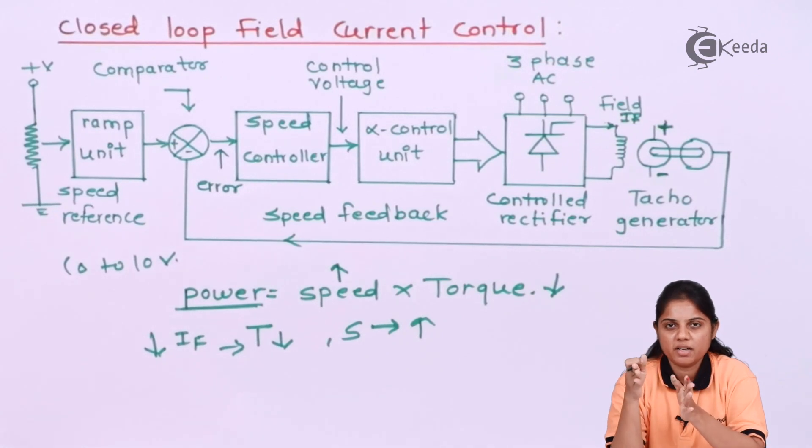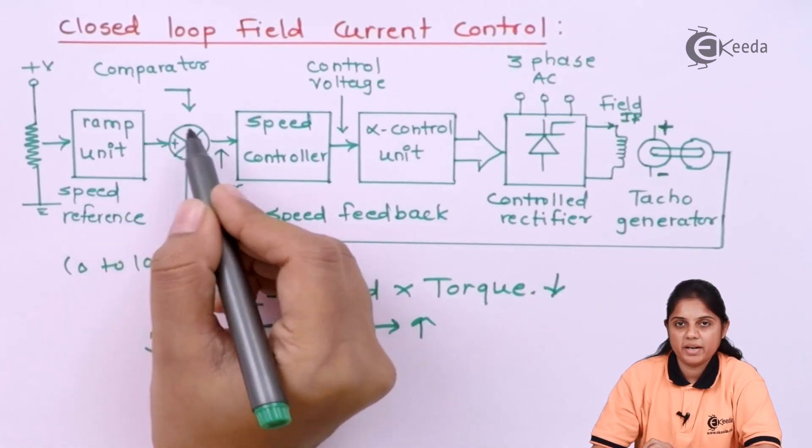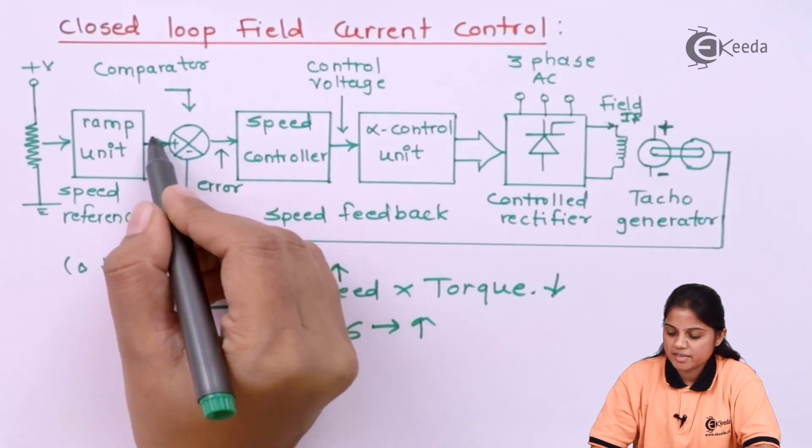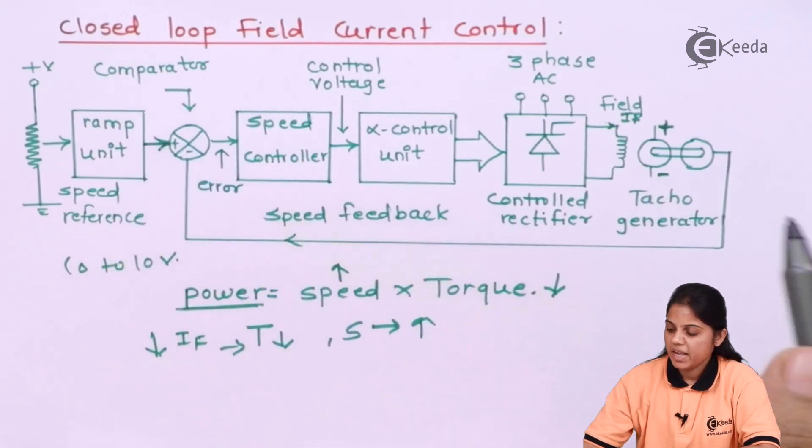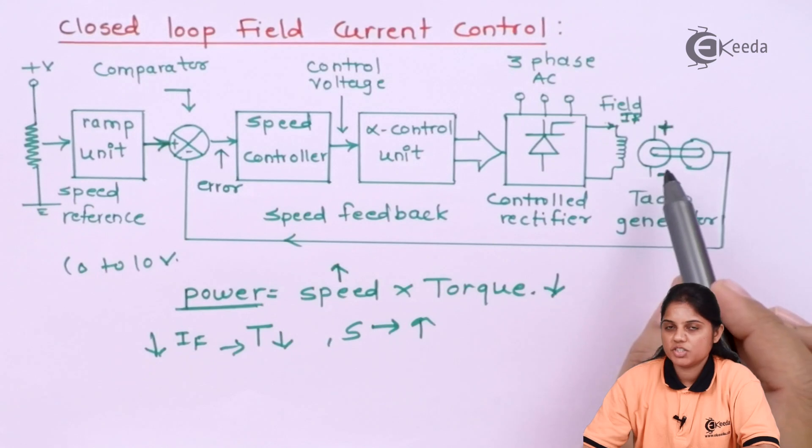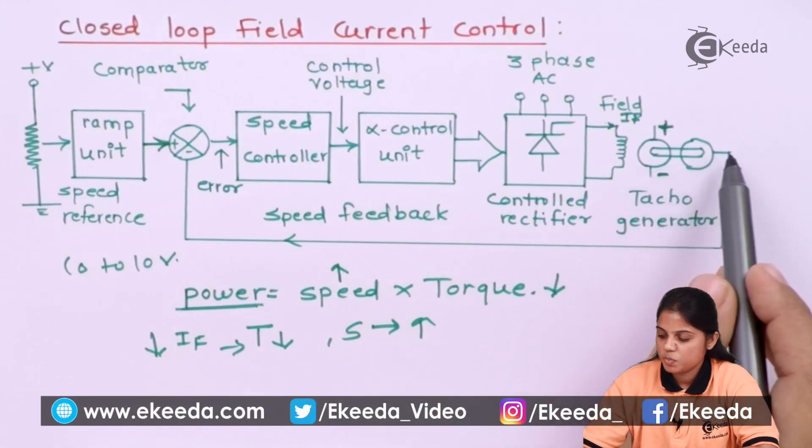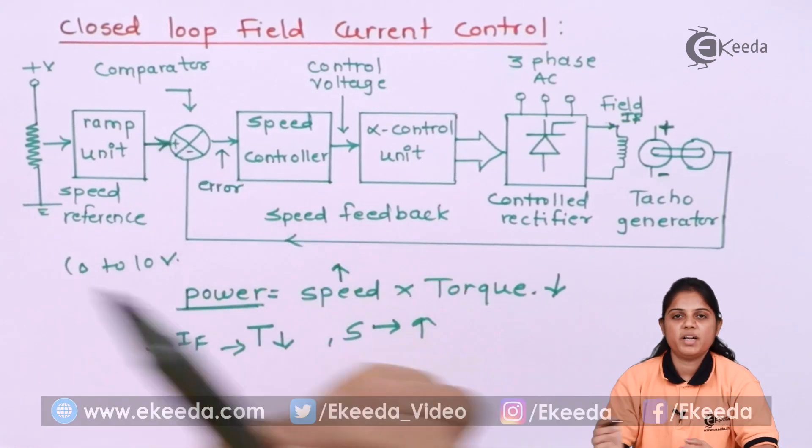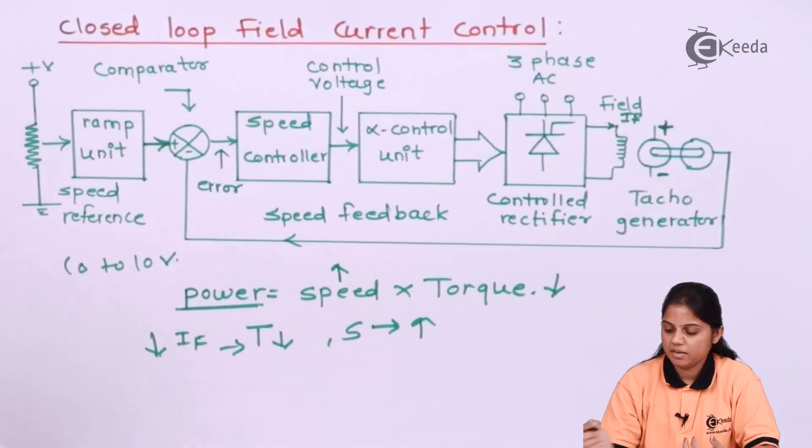That means speed is gradually increasing and that speed is given to the comparator to compare with the actual speed. So here what you are getting at this point is nothing but your reference speed. That is given to the comparator. And from the tachogenerator which is connected to the armature winding, you will get the speed of the actual motor and that will be fed back. If the actual speed and the reference speed are different, it will produce an error.